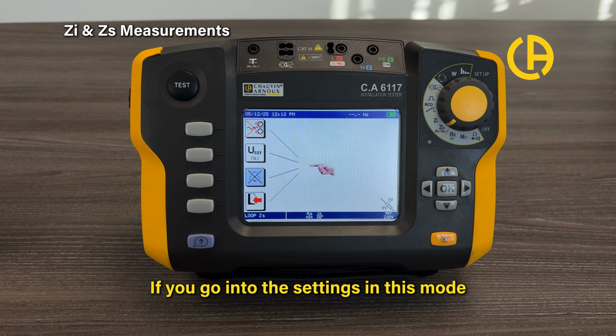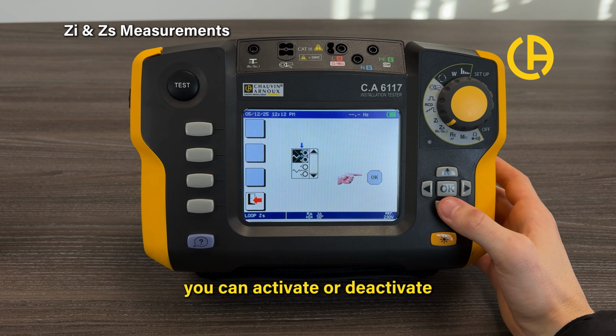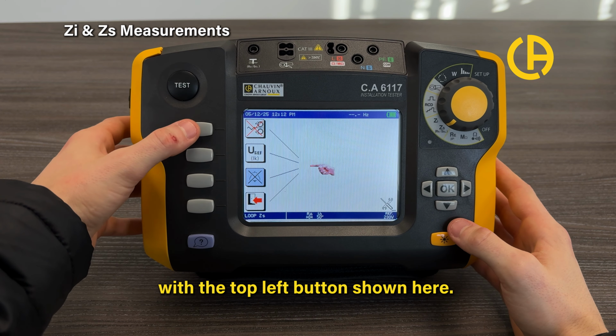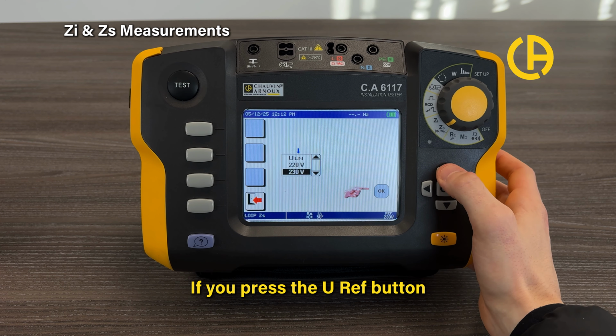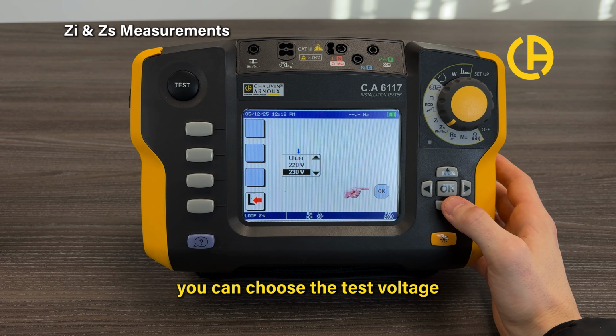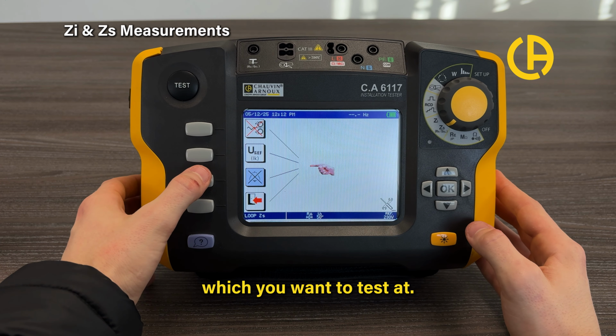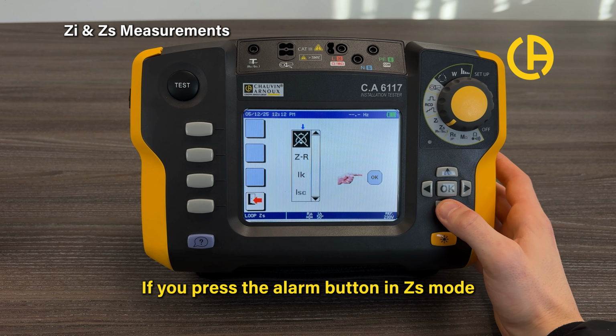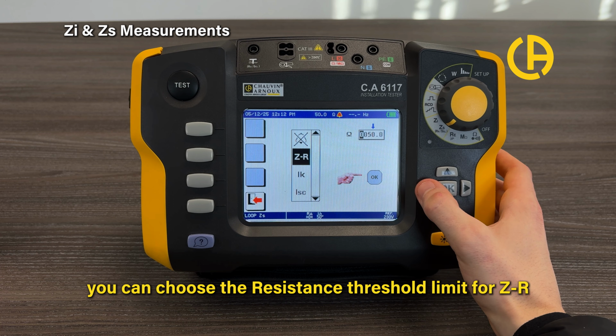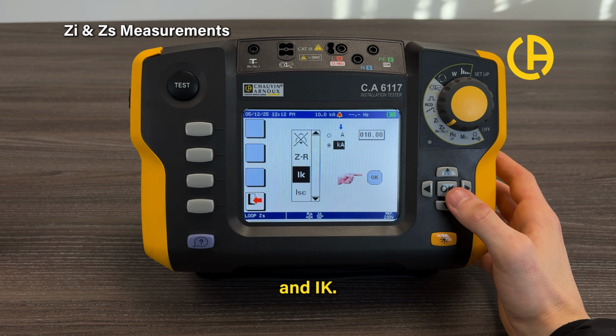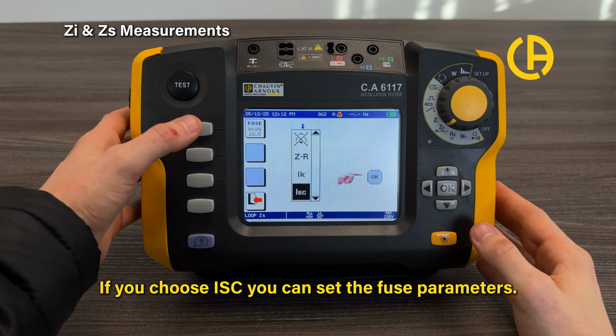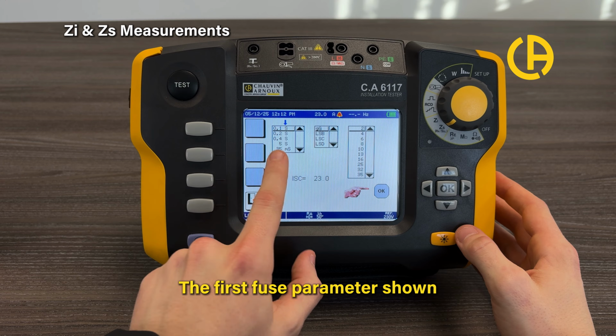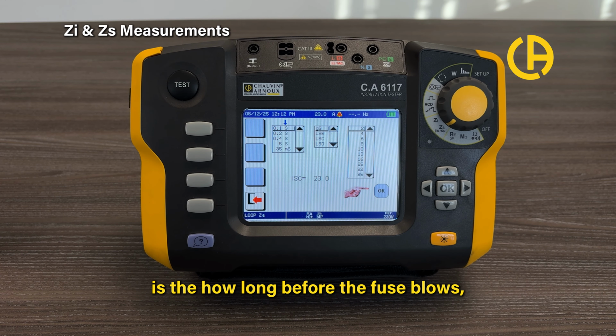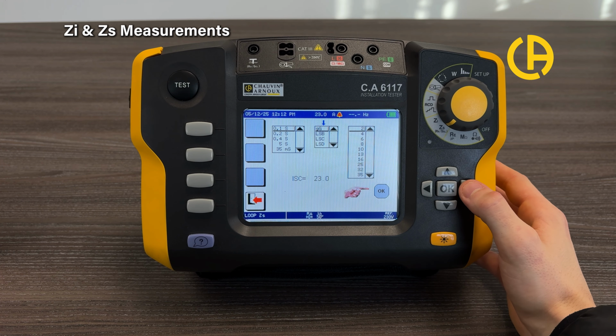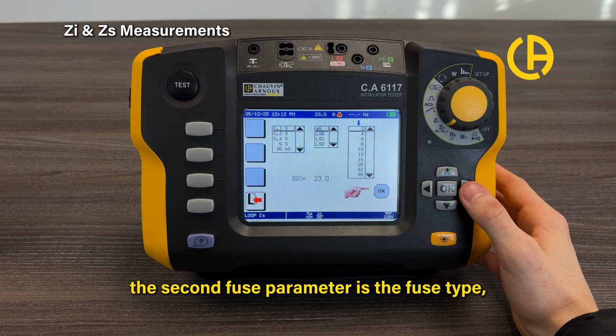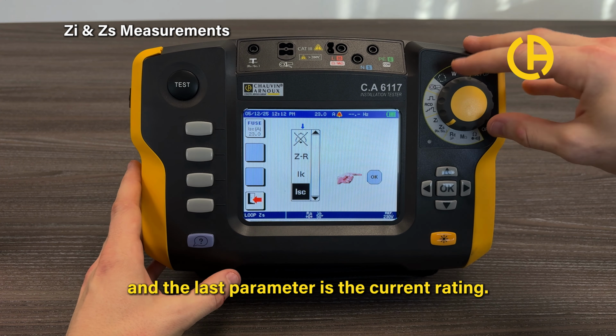If you go into the settings in this mode, you can activate or deactivate the smoothing of the signal with the top left button shown here. If you press the U-Ref button, you can choose the test voltage which you want to test at. If you press the alarm button in ZS mode, you can choose the resistance threshold limit for ZR and Ik. If you choose ISC, you can set the fuse parameters. The first fuse parameter shown is how long before the fuse blows. The second fuse parameter is the fuse type, and the last set parameter is the current rating.